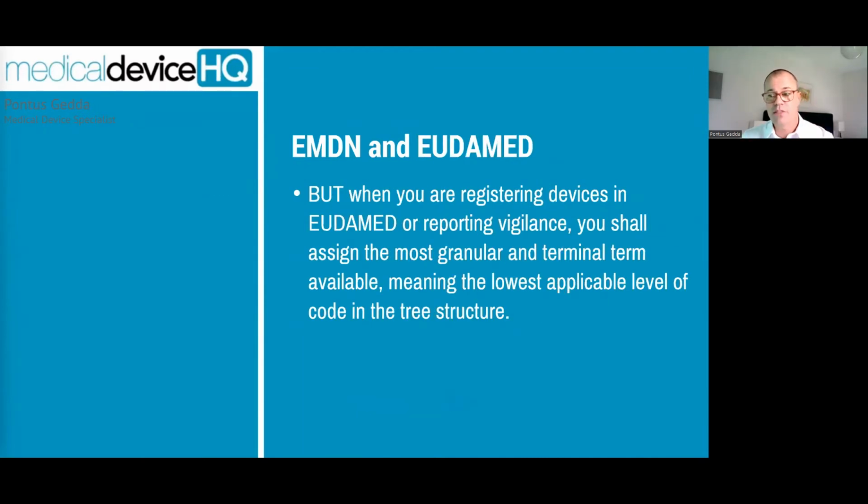But when you're registering your device in EUDAMED or reporting vigilance, you shall assign the most granular and terminal term available, meaning the lowest applicable level of code in the tree structure, going as far as possible on the web page where devices are defined with the EMDN codes, as I just showed.